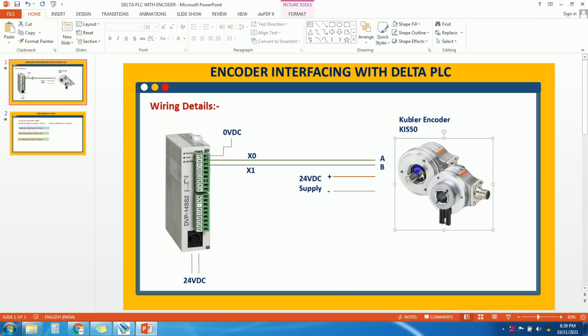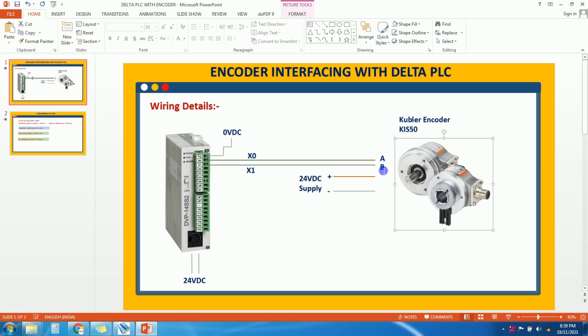We have a Delta PLC and a Kubler encoder — the KIS50 is the model number for the encoder. For wiring the PLC and encoder, on the encoder side we have plus 24V supply and minus 24V supply. We need to give 24V DC supply to the encoder, since the PLC working voltage is 24V. At the encoder side we have phase A and phase B — these are the encoder outputs that give pulses to the PLC.